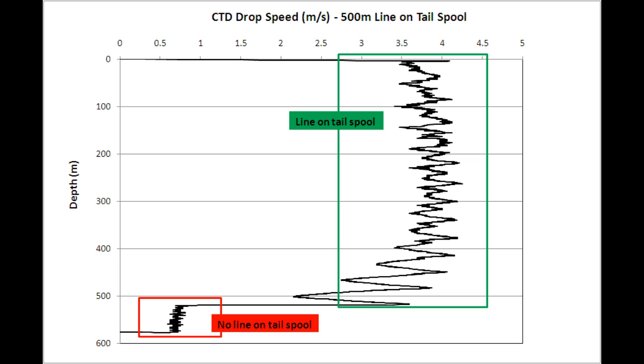until all of the 500 meters of line have been paid off the tail spool. And you'll see at about 510 meters the drop speed reduces from 2.5 to 3.5 meters per second, when the line is spooling off the tail, down to about 0.6 meters per second. That sharp break in speed is when all the line is paid off the tail spool, and now the probe is simply pulling line through the water, eventually off the winch.